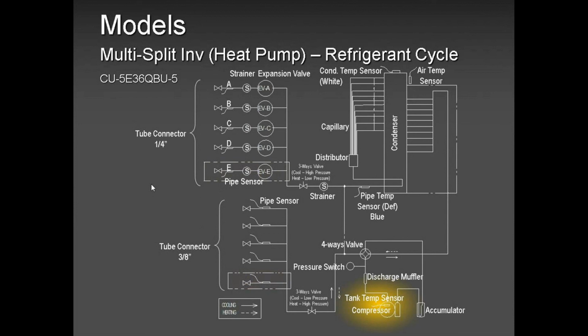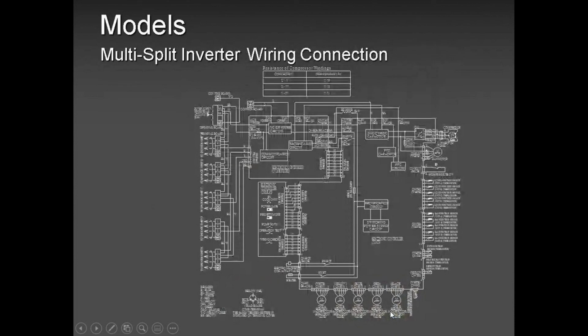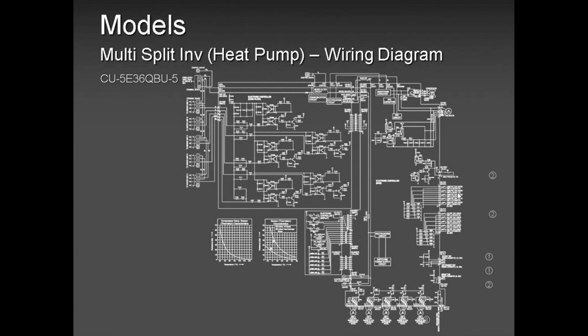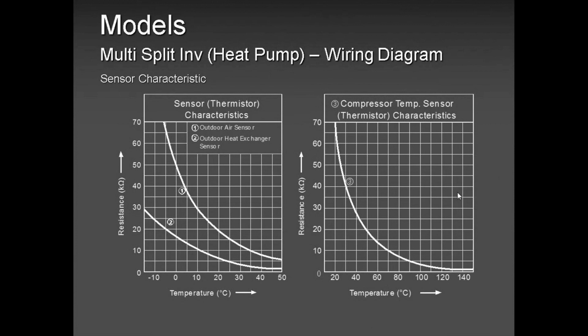So when you're done with your piping, wiring, and commissioning, don't run all units at the same time. Start 1 unit, let it run for 5 minutes, and if it's giving you nice heat or cold air, then switch that unit off, move to the next one, and to the next one, and to the next one. Once you know you have not crossed any wires or pipes, then you can run them all together. Many guys call me, and when I tell them you crossed the pipes or the wires, they tell me, but Paul, it ran the whole of winter. Because in heat mode, this error code does not show up. It shows up in cool mode.